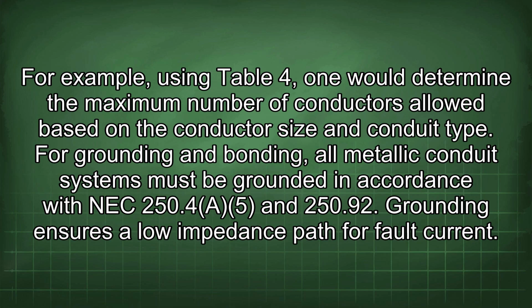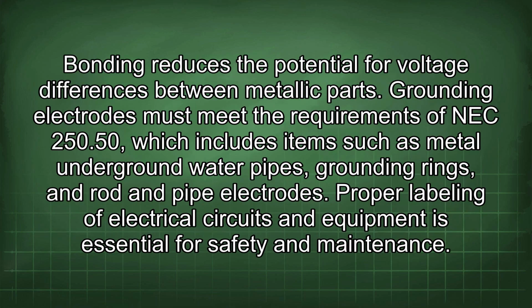For example, using Table 4, one would determine the maximum number of conductors allowed based on the conductor size and conduit type. For grounding and bonding, all metallic conduit systems must be grounded in accordance with NEC 250.4(A)(5) and 250.92. Grounding ensures a low impedance path for fault current. Bonding reduces the potential for voltage differences between metallic parts. Grounding electrodes must meet the requirements of NEC 250.50, which includes items such as metal underground water pipes, grounding rings, and rod and pipe electrodes.